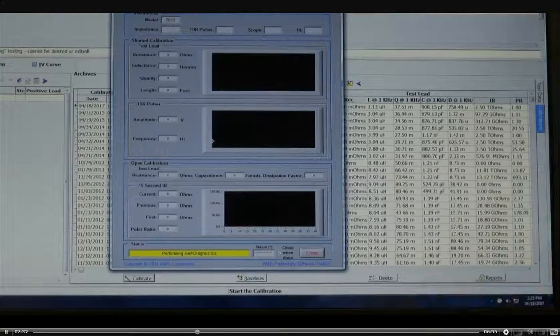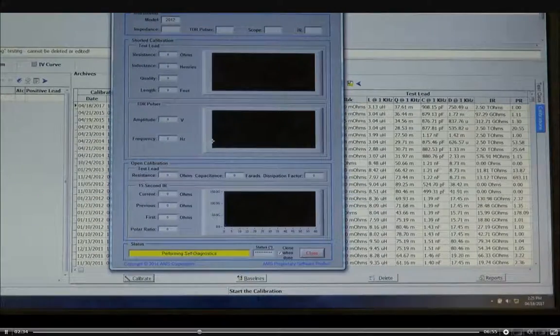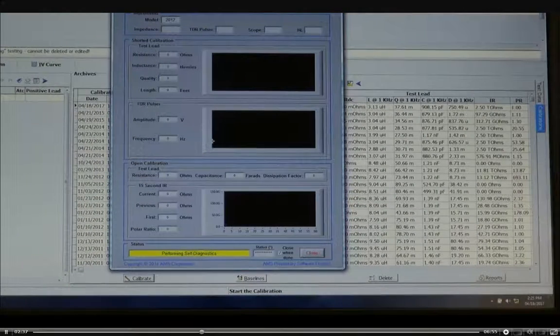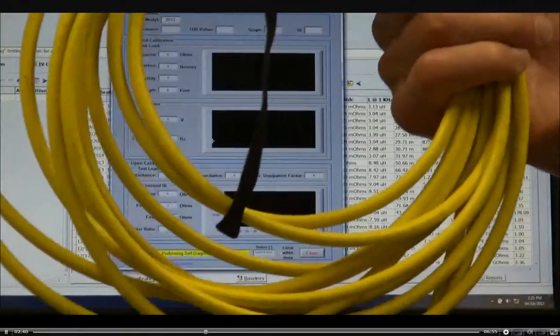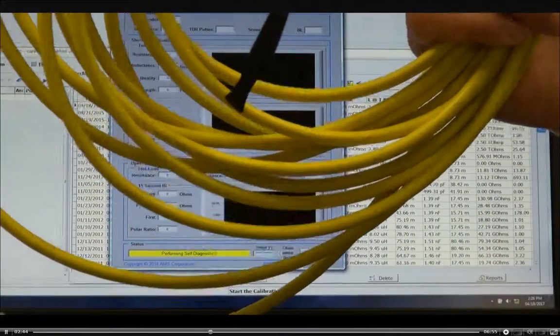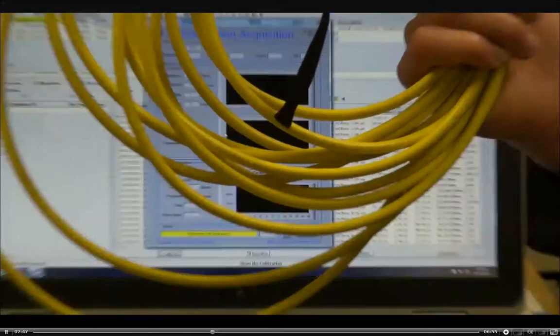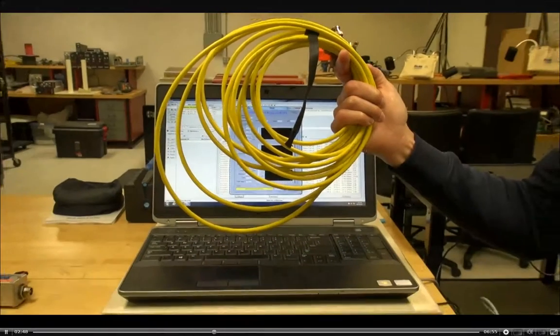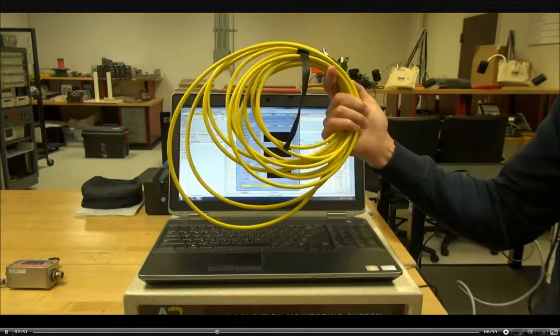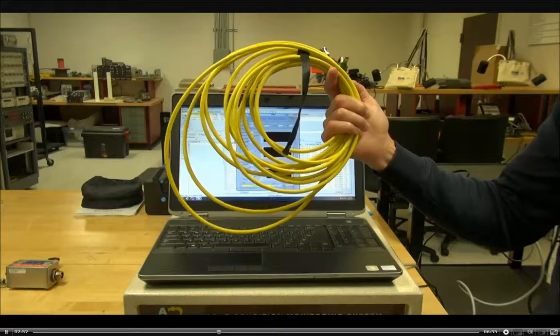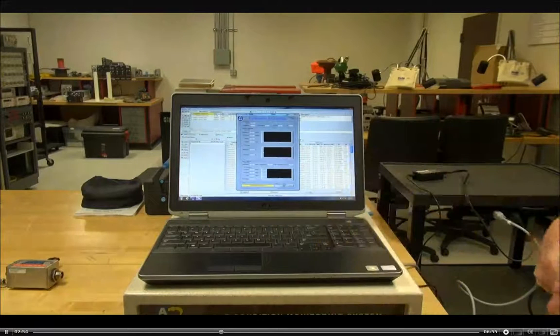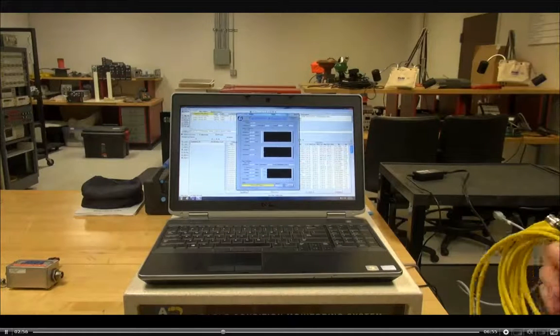While that's running its course, the next thing we're going to do is hook up the test leads. So what we're talking about, whatever test leads you choose to use, these ones are about 20 feet long. It's the ones that we normally use. When you do your calibration, it's basically going to null out these 20-foot leads so that it'll ignore them when you're doing your calibration. So that's what we're talking about doing. So it's finishing up the calibration of the box.